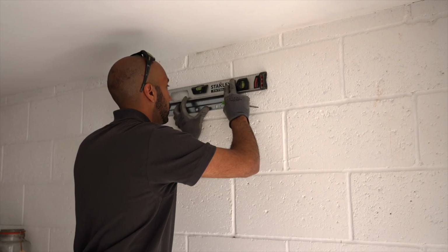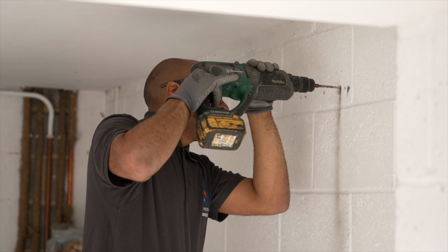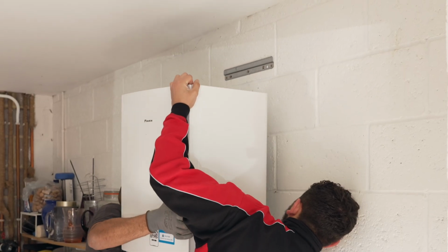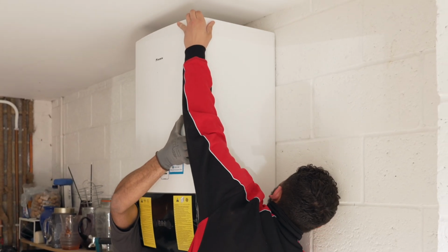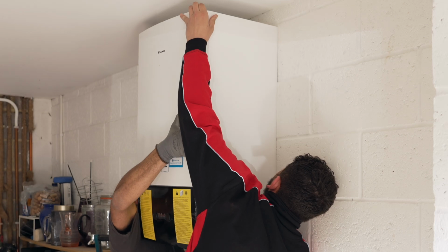installation. The bracket to hang the Hydrobox is located within the box and can now be mounted to the wall. Simply use the two slotted holes in the bracket to fix this, and then you will notice that there is a diamond-shaped hole in the upper mounting part of the bracket. Make sure that you've drilled a hole and put a plug in before lifting the Hydrobox into place, and we will fix through the unit to secure it once it's hanging.